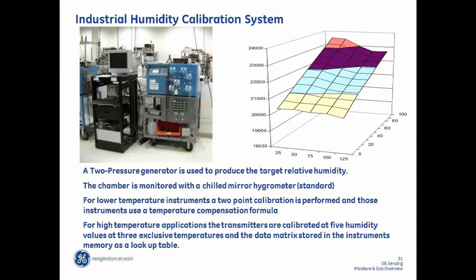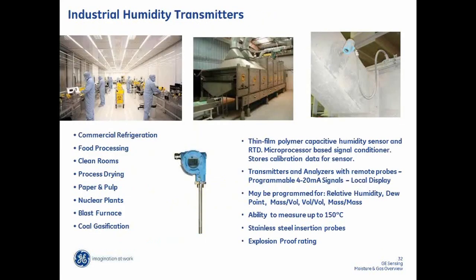And these are typically just assembled in a stainless steel probe with a header that puts out a linear 4 to 20 milliamp signal. And they're used in a whole host of applications, everything from ambient air to cement making to food processing, where, for example, drying nuts or even curing the adhesive on sandpaper, these sensors might be applied to those process controls.